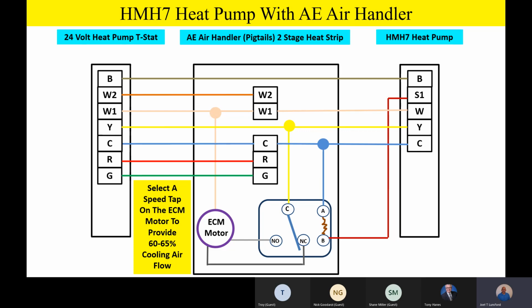On the normally open contact on the relay, we're going to go over to the ECM motor and select a speed tap that's going to give us about 60% airflow, 60 to 65% airflow. Now, I've had some questions on this from customers. They said, "Well, Joel, I'm kind of stuck in the middle. With my ECM motor, my ductwork and all that, on speed tap number 3 I've got 72% airflow, and on speed tap number 2 I've got 58% airflow. Which one do I take?"